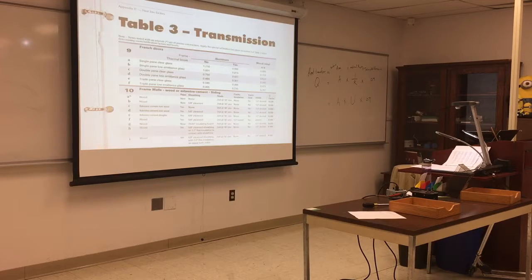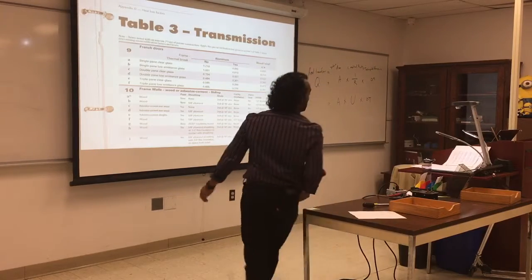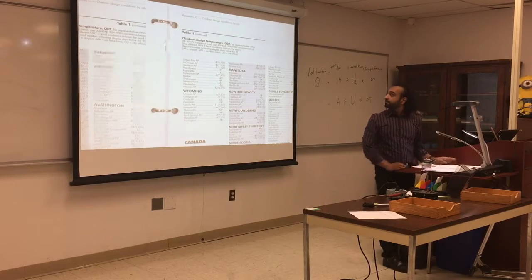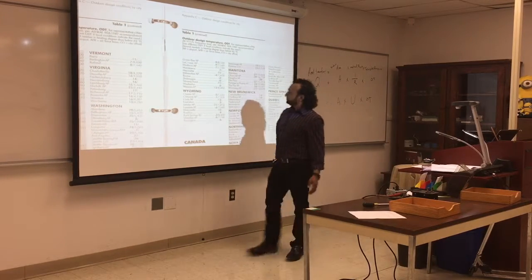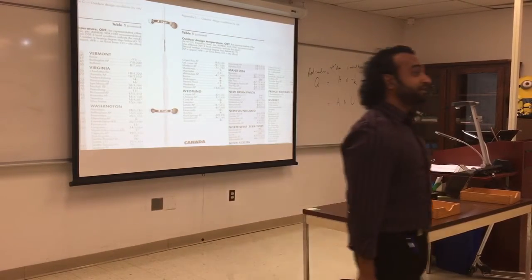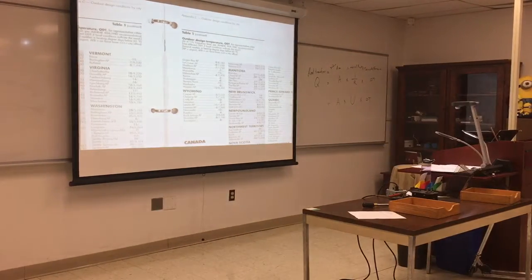Highest or lowest. Yeah. So you're going to go in the book. They also give you a list of big cities by state. Of course, this book is from the 60s. This thing has changed a lot, so you can look up Springfield, for example, the coldest day of the year, they designed for 0, and the hottest day of the year, they'll say 95.